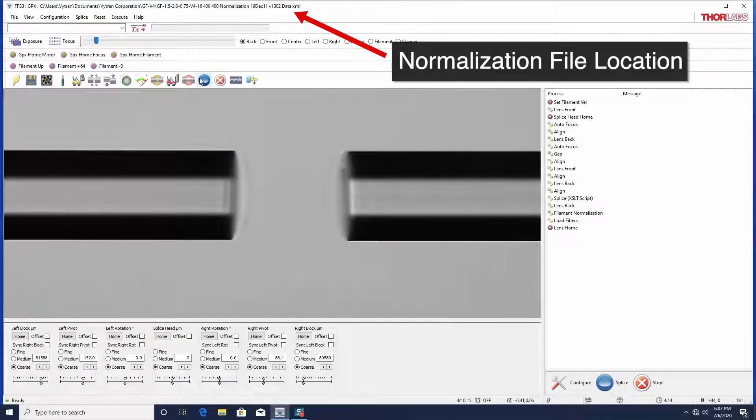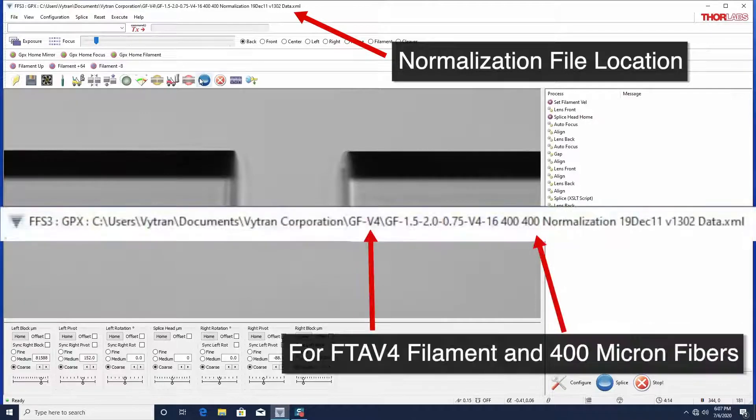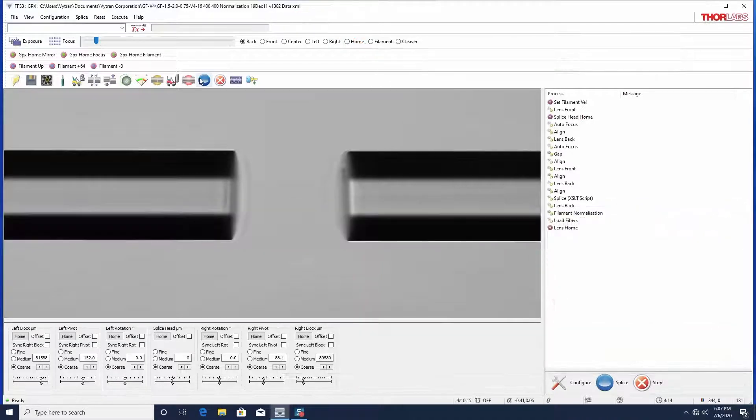Normalization files for common combinations of filament type and fiber size are pre-installed on the computer that ships with the unit. You should select a normalization file that corresponds to the type of filament you are using and with a fiber diameter that is closest to the one you intend to use for your application.